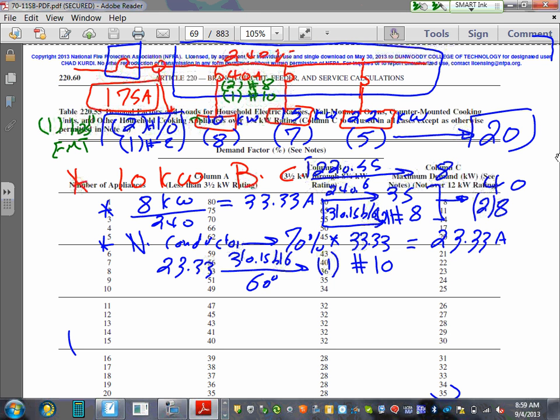Okay. So that's the size for this range. Any comments, any questions? The first range, we did not do the neutral derating because I don't want to confuse you, but we should have done a neutral derating. Always neutral derating for ranges, always, 70%. Magic number. Where did it come from?